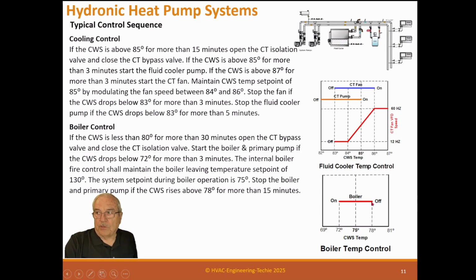Remember that we're trying to keep away from these temperatures of 83 to 86. And here we're 81 to 69. So there's a difference in those temperature ranges. Now remember, all these ranges I've given you are changeable. This is just my recommendation, but you could tighten these up or lengthen them out depending on how you want to operate. And of course, it has to be within a range that the heat pumps can actually use the water. 72 is fine, and this 87 is fine. If you think about it, it's just like a package air conditioning unit outside, and the outside temperature is 87 degrees. That's an easy place for it to be. So water-cooled provides high energy efficiency because the condensing temperatures are reasonable.